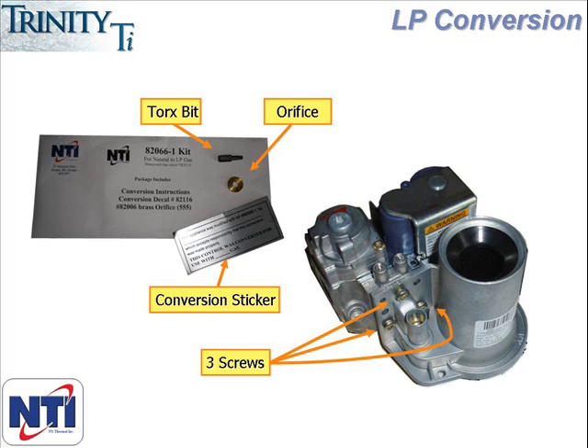an orifice to be placed between the gas valve and the venturi, and a sticker to indicate the unit has been converted to LP. It is very important that any unit being used with LP be properly converted — it's not enough to simply perform a combustion test. The proper orifice needs to be inserted.